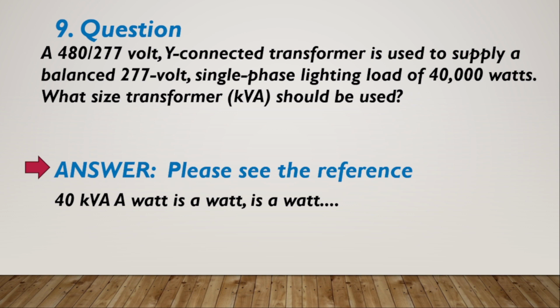Question number 9. A 480/277 volt Y-connected transformer is used to supply a balanced 277 volt single phase lighting load of 40,000 watts. What size transformer kVA should be used? Please see the reference.